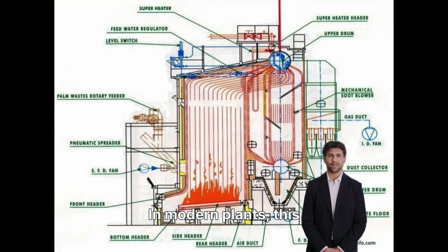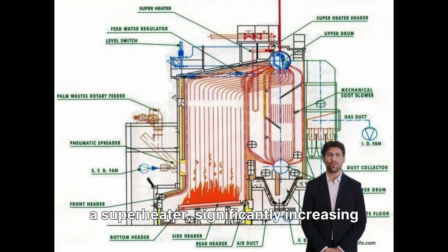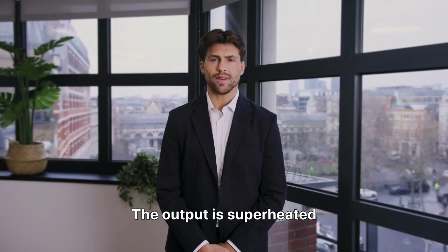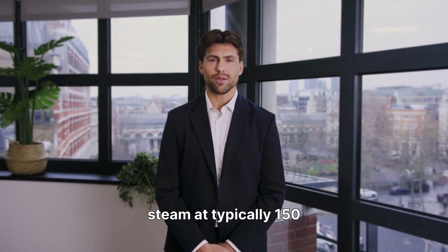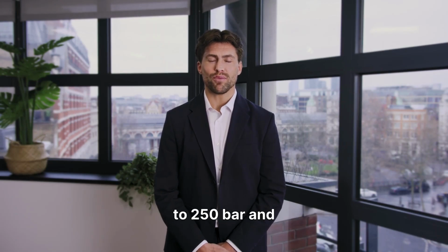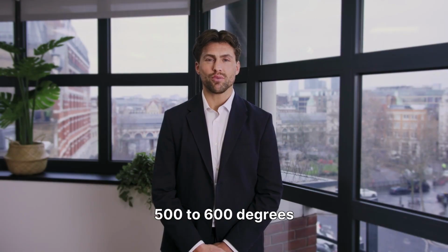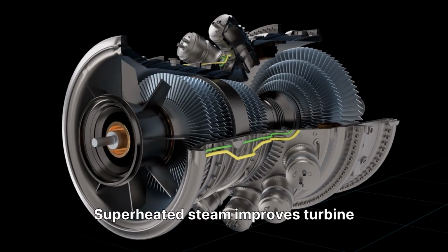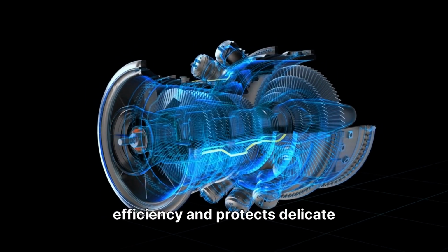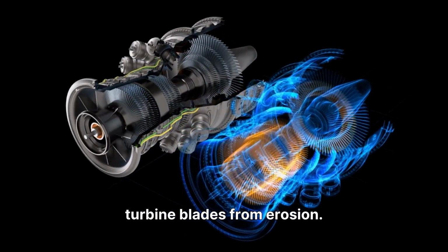In modern plants, this wet steam passes through a superheater, significantly increasing its temperature and pressure. The output is superheated steam at typically 150 to 250 bar and 500 to 600 degrees Celsius. Superheated steam improves turbine efficiency and protects delicate turbine blades from erosion.